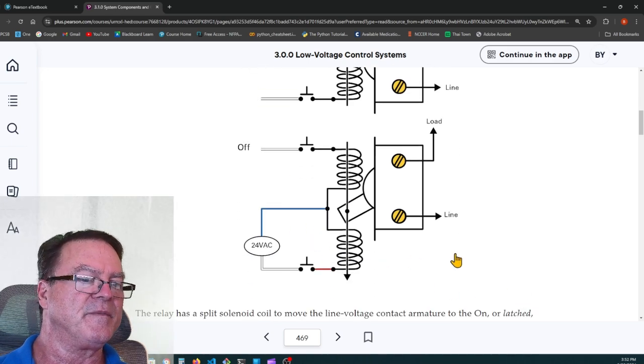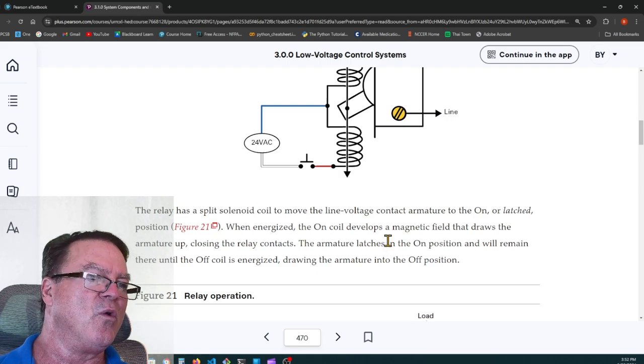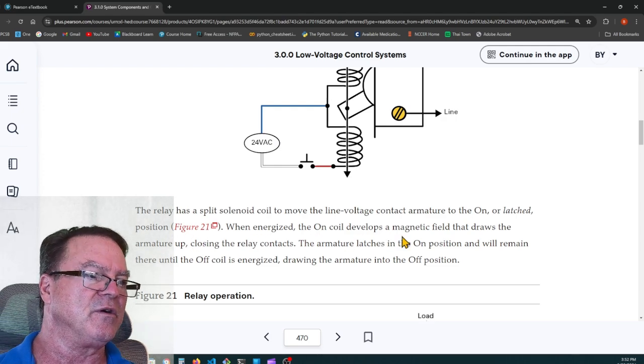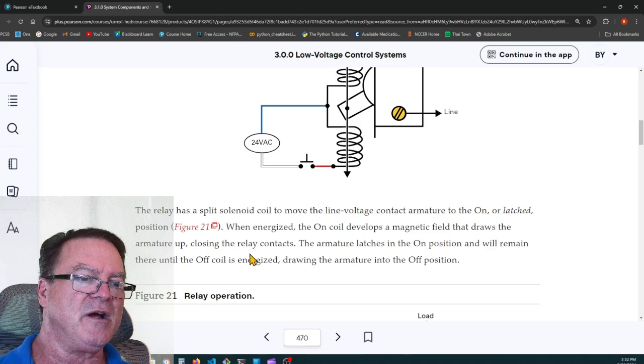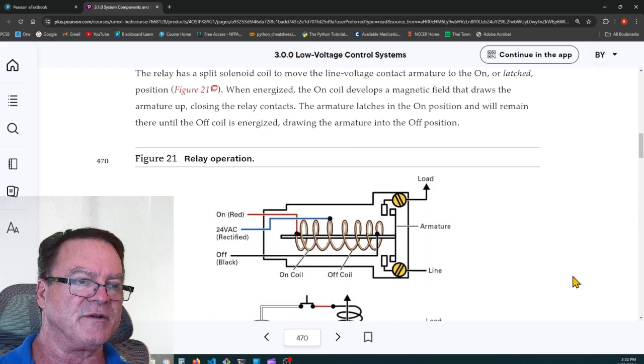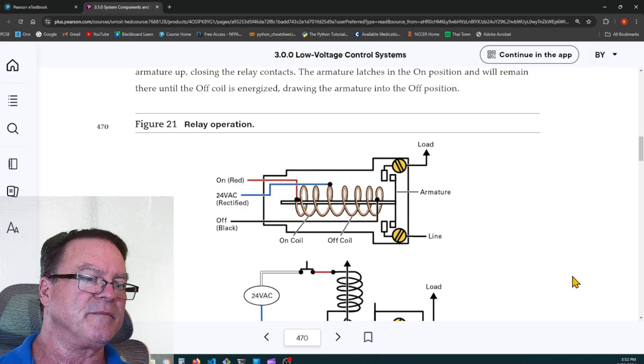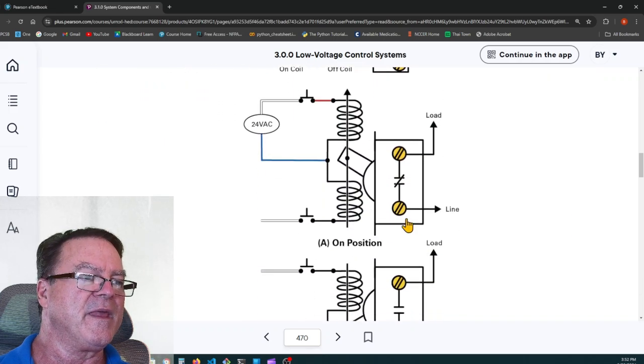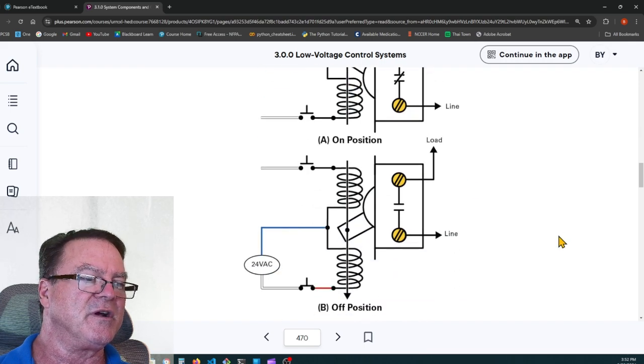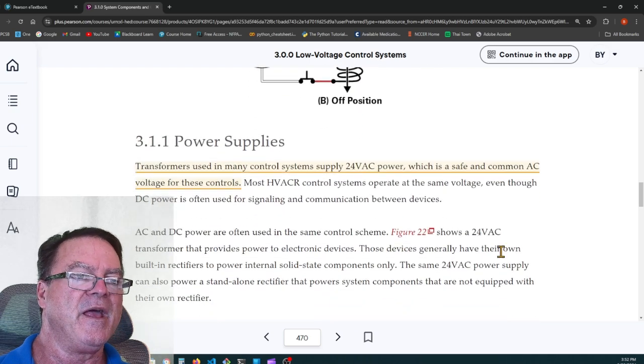There's the off position. Relay has a split solenoid coil to move the line voltage contact armature to the on or latched position. When energized, the on coil develops a magnetic field that draws the armature up, closing the relay contacts. The armature latches in the on position and will remain there until the off coil is energized, drawing the armature into the off position. So, relay operation. There again, they're making contact with the red circuit, bringing it on, pulling the plunger up, or the blue circuit, causing it to come down and turn it off.